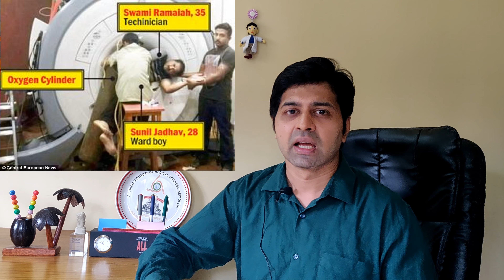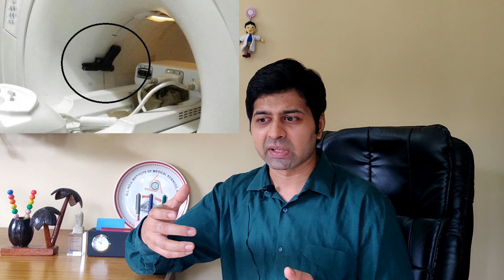In another incident, an oxygen cylinder was unknowingly kept inside the MRI room, and when the MRI machine was switched on, obviously it got yanked towards the machine, and on the way it hit the head of the child who was undergoing examination, leading to the death of the child. There was another incident where an old man by mistake took his walker inside the MRI room, and as expected, the walker got pulled. As a result, the old man lost balance, fell down, hit his head, eventually leading to the death of the person. There have been a few other incidents as well of oxygen cylinders being taken inside the room by mistake and people getting stuck between the machine and the oxygen cylinder. And there have also been incidents of even the guns of inspectors getting pulled and getting stuck at the MRI machine.